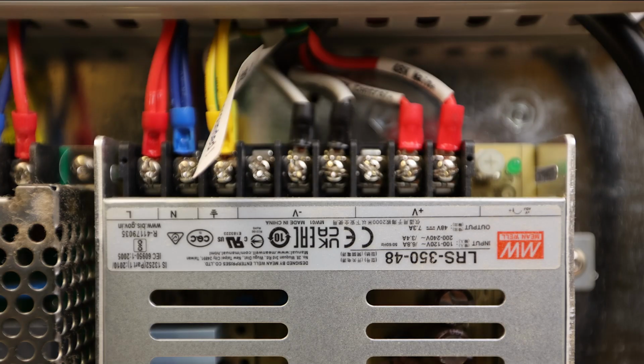Each power supply unit has a red line, blue neutral, and yellow ground wire powering the unit from the wall. They also feature the voltage terminals where the outgoing power is sent to the various components in our machine. Typically, these are composed of red positive terminals and black negative or common terminals. These will be important when we begin our testing.